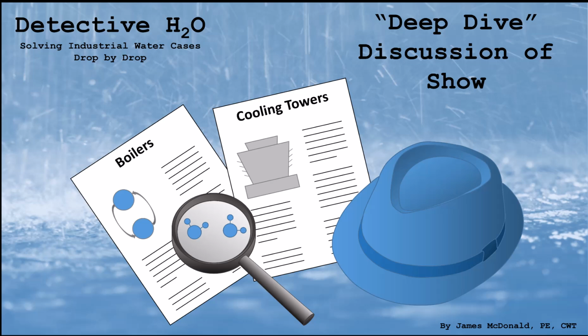So what does Detective H2O find? He notices that the slow rinse valve on the polisher isn't functioning properly. It seems like a minor thing, but it has a domino effect, because that malfunctioning valve allows salts and other impurities to slip through the polisher and contaminate the boiler feed water. It's one of those cases that really highlights how a small equipment failure can have a cascading effect.